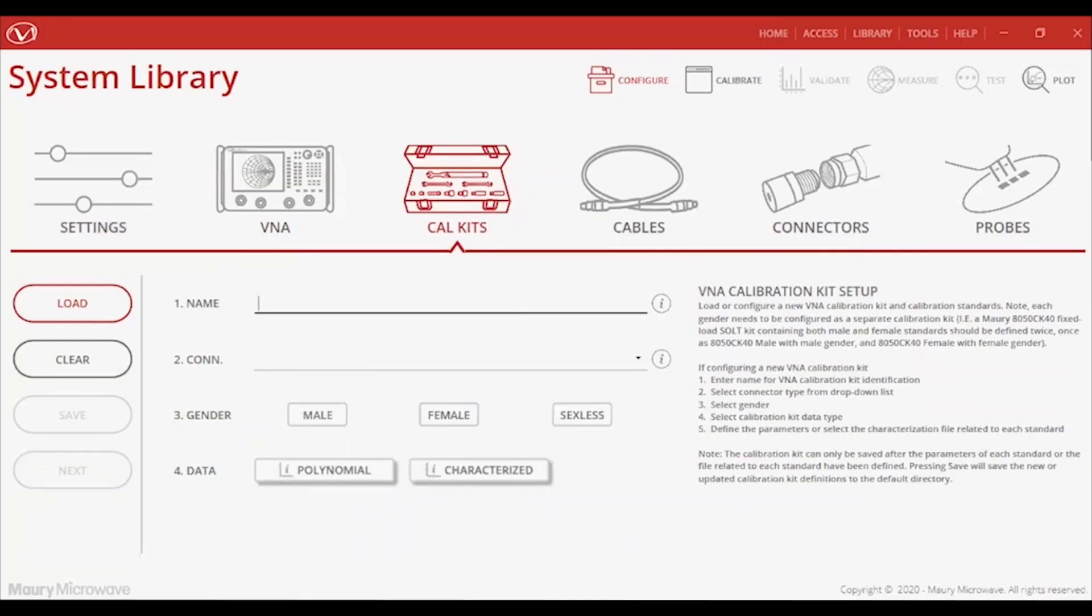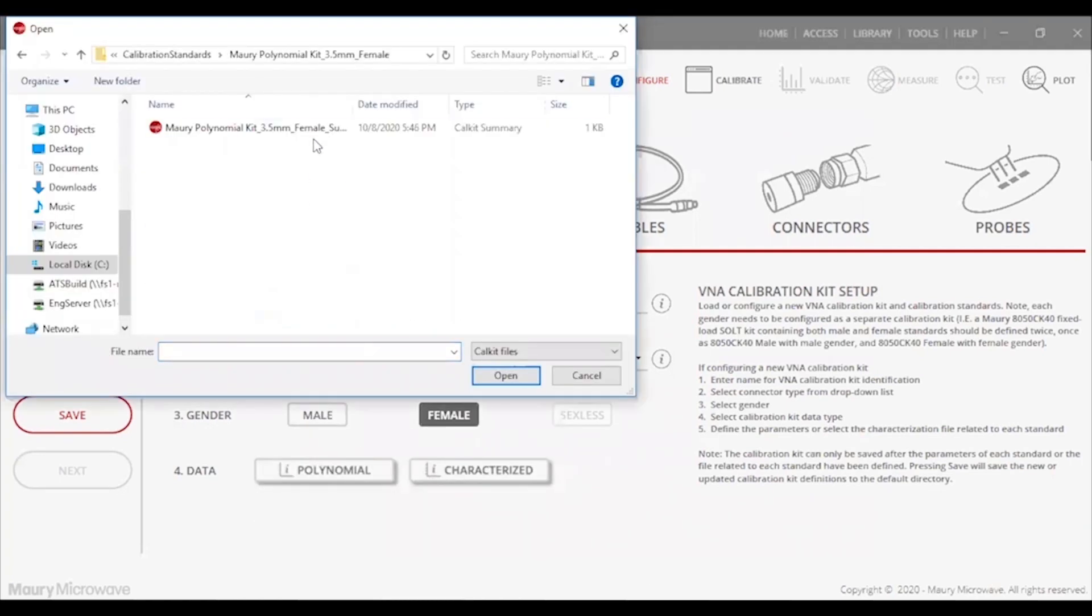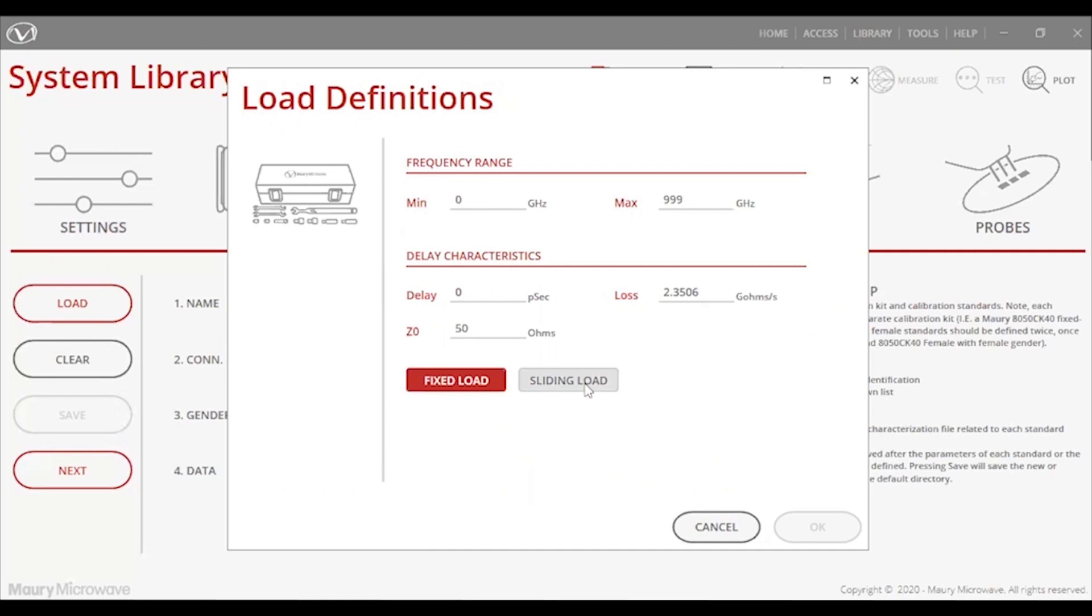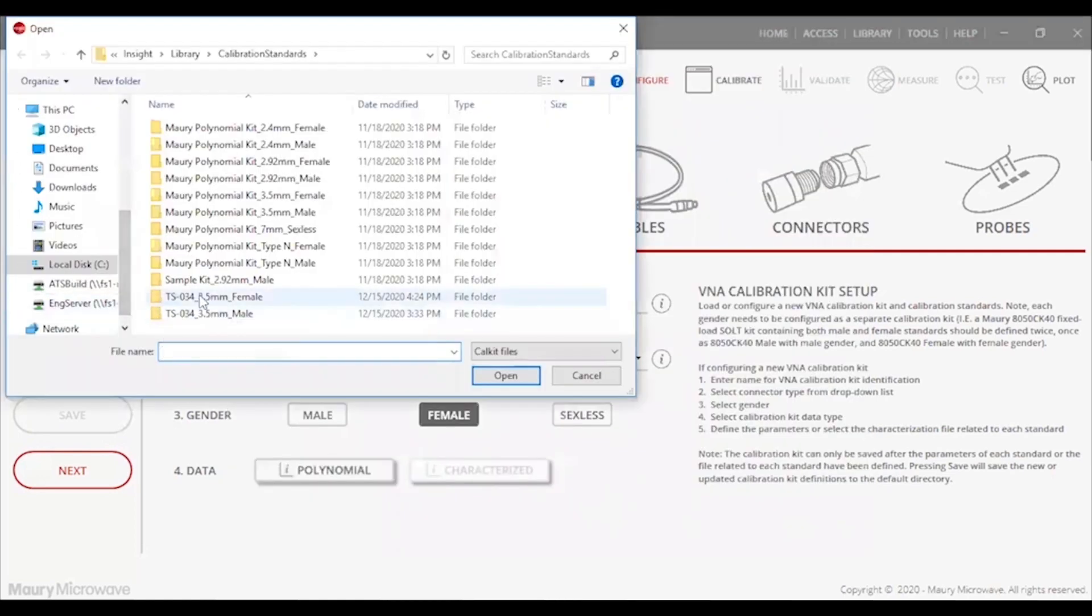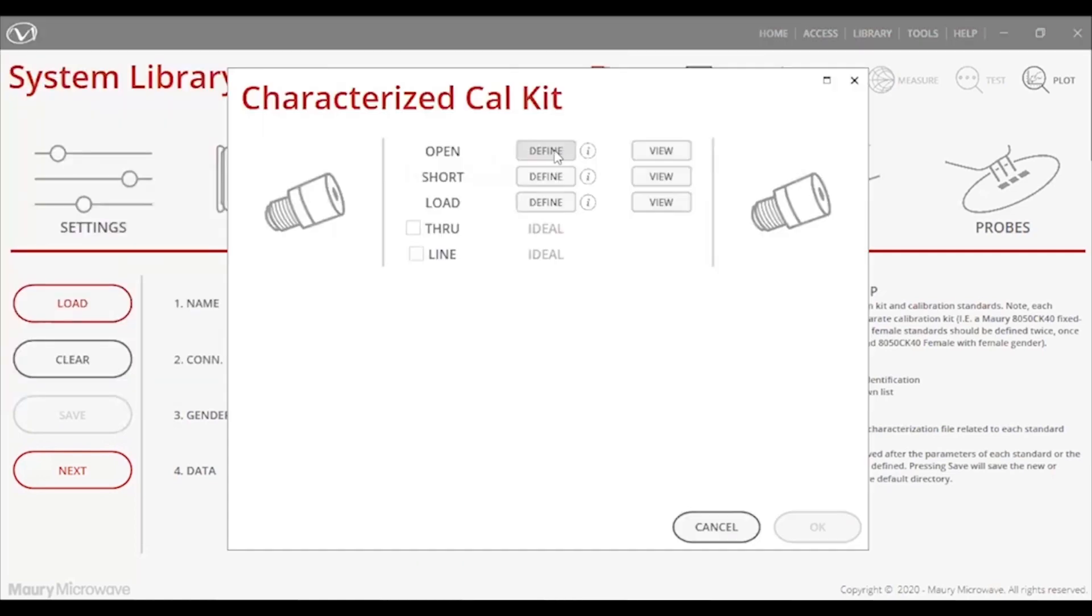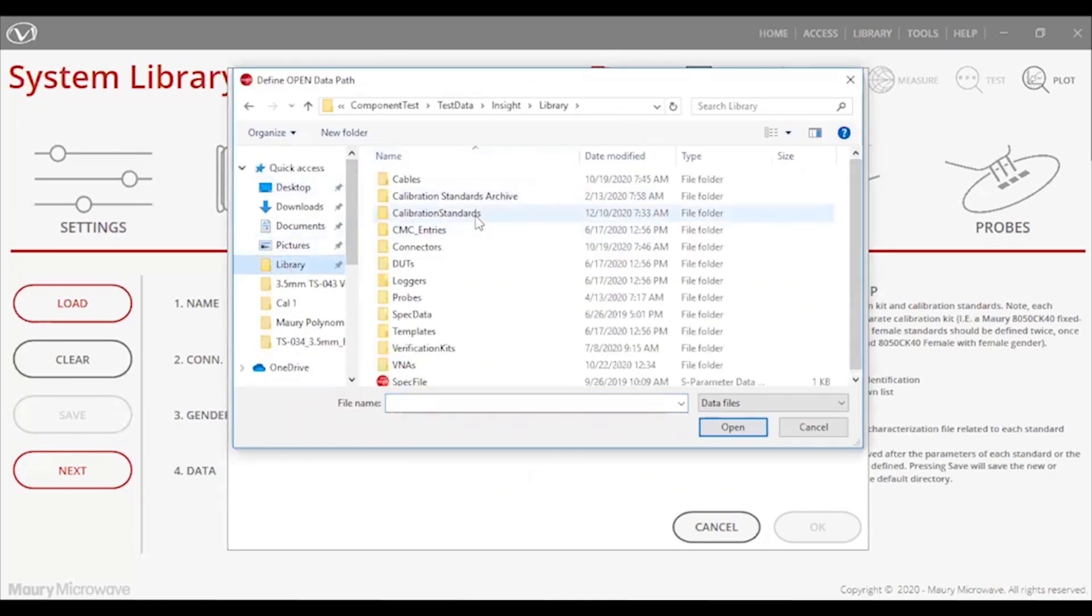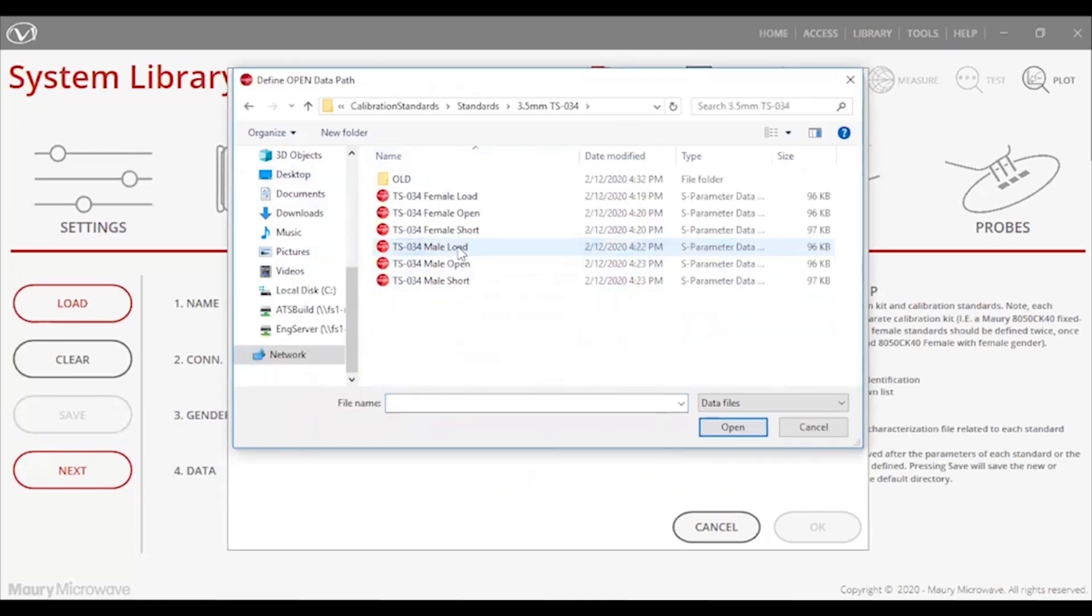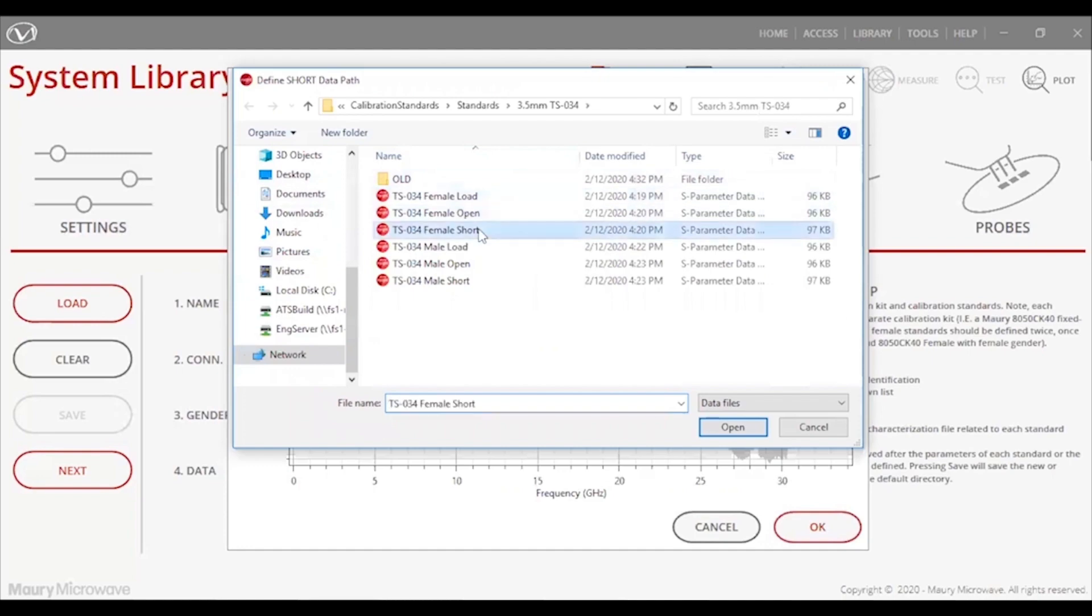In this tab, I can manage multiple VNA CalKits and types, including polynomial and characterized kits. InSight helps to take over the responsibilities of studying the CalKit definitions, storing that information in a centralized database and makes all CalKits and CalTypes compatible with all VNAs, even if not originally supported by the VNA, like my 8510.